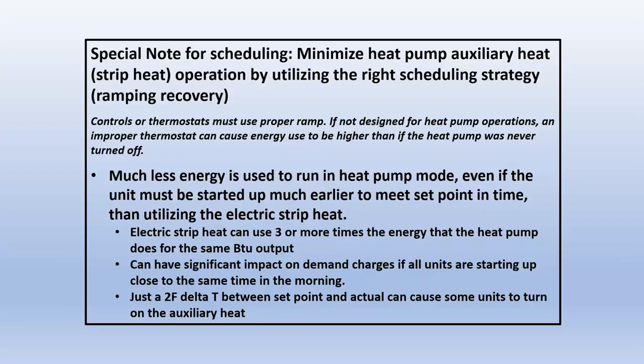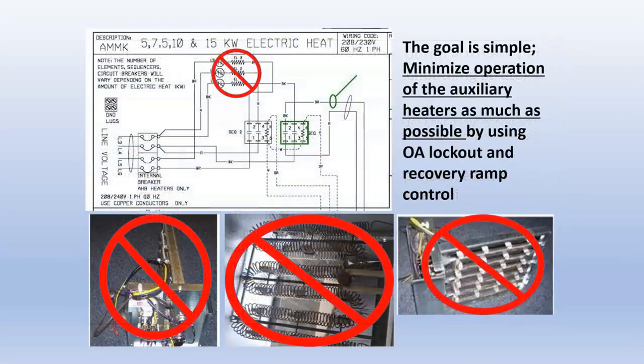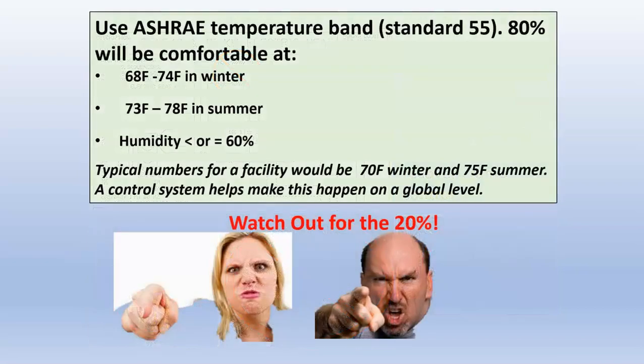But using the heat pump ramp, where the algorithm actually looks and decides, hey, I'm better off if I just leave this heat pump on. Or it realizes I'm dropping temperature to a certain point. It's like, I'm going to start the heat pump now in the middle of the night, rather than wait till the morning and fire up those aux heaters. Goal's real simple: minimize operation of it. And sometimes some schools or businesses just lock them out. They'll take them out of the system and let the BAS figure out how to run without them. You can do that if you don't get an extreme cold. If you get really cold areas, you can't get away with it.